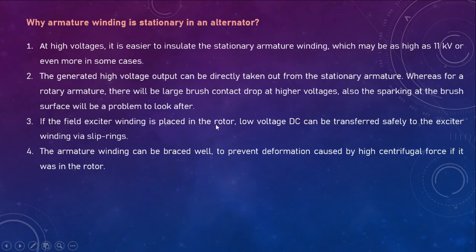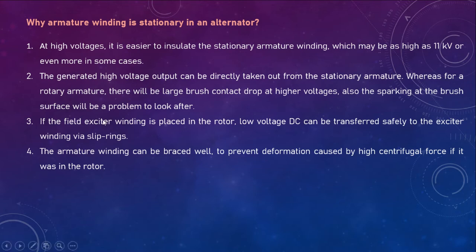If the field exciter winding is placed in the rotor, low voltage DC can be transferred safely to the exciter winding via slip rings. Since field windings are placed in the rotor side and are rotating, low voltage DC supply can be fed to excite the rotor without any problem.